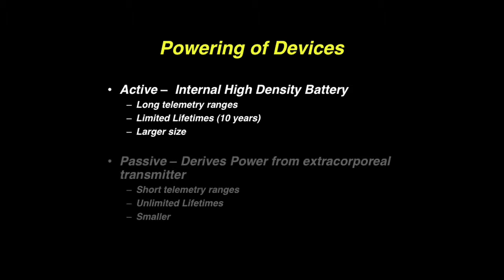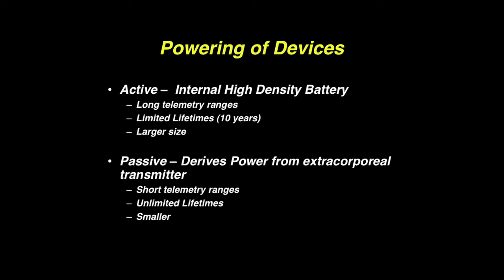Another method is called passive. And this derives power from an extracorporeal transmitter, which means that there's a transmission device outside of the body that, in a sense, beams the power in wirelessly. The advantage is that you don't have the internal battery, so you can have unlimited lifetimes. The disadvantage is it's hard to get the energy in, so we often have short telemetry ranges that we have to deal with. But you can make things much smaller.